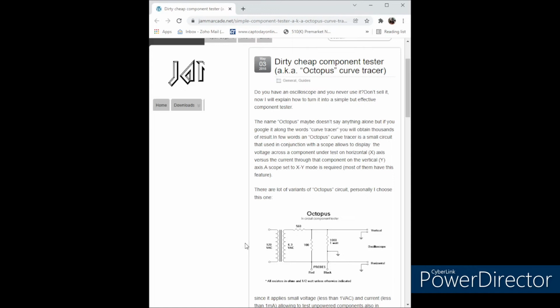So I had everything, but of course on this one you needed a separate signal source. A sinusoidal signal generator is needed, and I think this one uses the mains voltage, 120 volts, to step down at 50 hertz to 6.3, and then drive that sinusoidal waveform through the component. That's how they are doing it. But I had my own signal generator, which is the Huntron Tracker 2000. It has multiple frequencies. It can output 50 hertz, 400 hertz, and 2000 hertz.